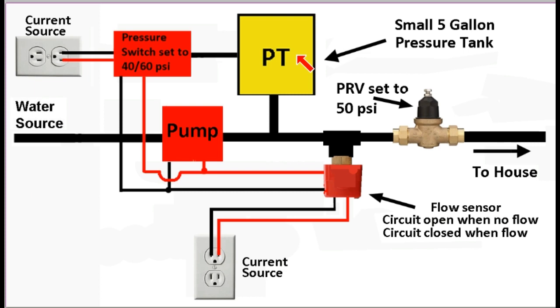We're able to avoid the problems that the CSV has by adding a new component called a flow sensor. A flow sensor is a piece of equipment that you can install in the pipe, and it detects when there's a flow of water. So when there's no flow of water, the circuit is open, which means no electricity can pass through the switch. And when it detects water, the switch is closed. Now, if you look at this pump, it's set up so that the pump will go on in two different cases. If the flow detector is detecting water being used, the pump will go on. If the pressure switch finds that the pressure goes below 40, the pressure switch will turn on the pump until the pressure tank reaches 60.